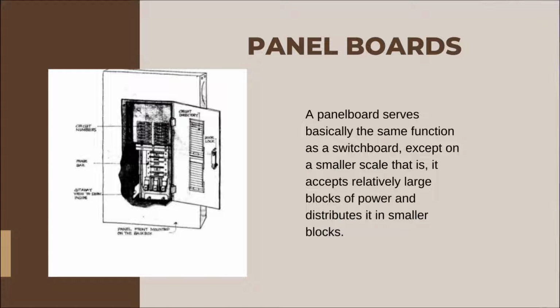Panel boards. A panel board serves basically the same function as a switchboard, except on a smaller scale. That is, it accepts a relatively large block of power and distributes it in smaller blocks. So, a panel board is a component of an electrical distribution system which divides an electrical power feed into branch circuits while providing a protective circuit breaker or fuse for each circuit. In a common enclosure, a panel board serves to protect branch circuits from overloads and short circuits.